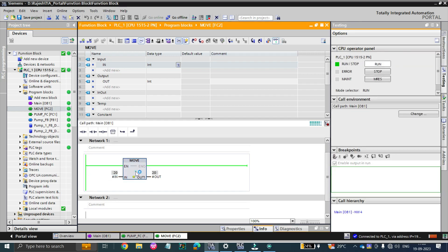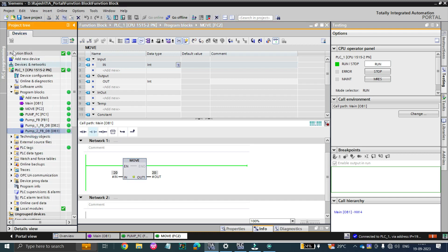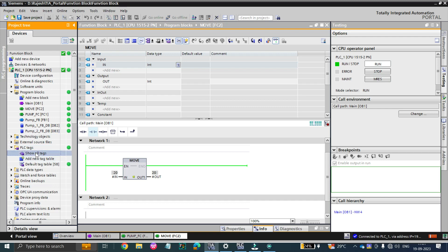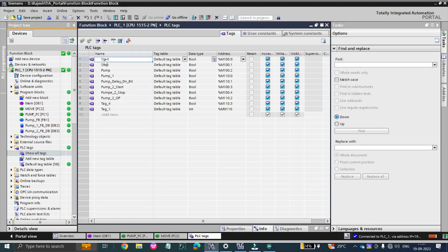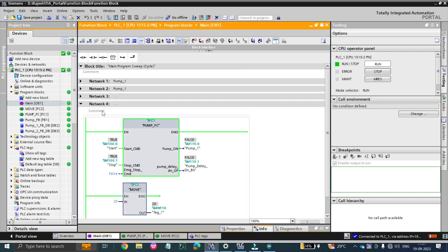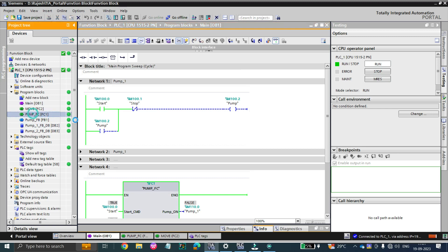You can see 20 is being copied to MW110 — the function is working. If you have this kind of logic — move, divide, or math calculations — there's no need for a static component. This can be done using local tags. Local tags can only be called within the same function, while global tags are stored outside — like DBs and PLC tags in the project tree. PLC tags like start, stop, M100.0 are global type, which can be called anywhere — in main, in pump FC.